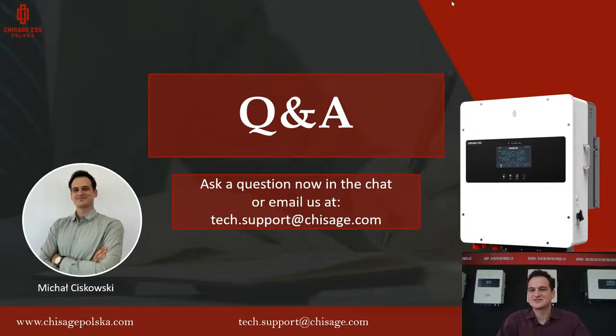Yes and no. Okay, for the load we can put all the power of the inverter. So yes, for a 14 kilowatt Mars we can put a 14 kilowatt load. For 5 kilowatt it is just the unbalanced load, so you can have a maximum of 5 kilowatt per phase. You can put 5 on phase number 1 and 0 on phases number 2 and 3, and the inverter will power this, maximum 5 kilowatt. But for the whole load we can go with 14 if we have Mars 14. For Mars 10, of course, it will be 10 kilowatt. So all the inverter power goes to the load port, but maximum 5 kilowatt per phase, unbalanced output.